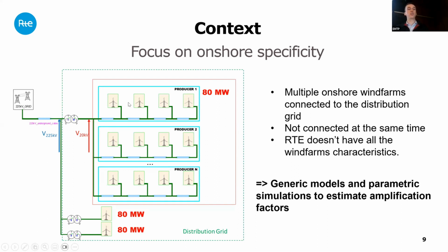RTE prepares the connection, but the producers come online at different times. Since the producers are connected to the distribution grid, RTE, as the transmission grid operator, doesn't have all the wind farm characteristics. So to estimate the amplification factors, we need generic models and must carry out parametric simulations to calculate them.